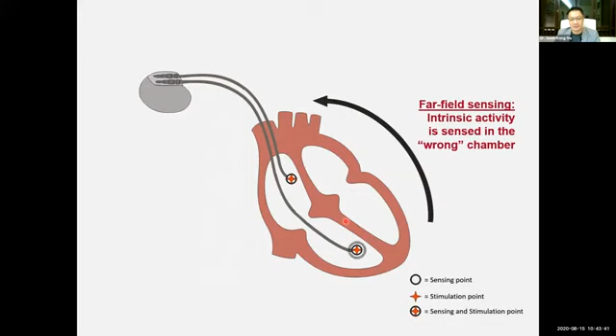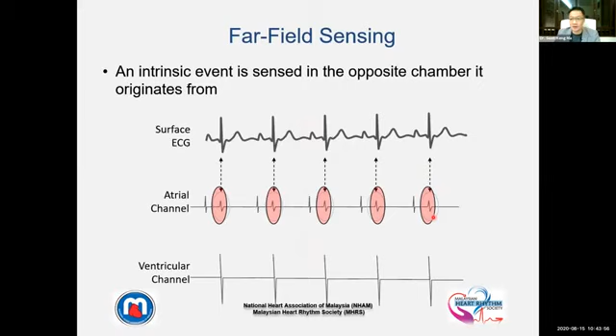And you can see here, the atrial channel always senses the QRS complex, which should be happening in the ventricular channel, but it picks up as a signal in the atrial channel. It looks like a 2-to-1 connection here. How to overcome this problem? Now, in the interest of time, I just move on. We skip the poll here. It is to increase the PVAB here, because you need to increase the atrial channel blanking period so that it won't sense the signal which is happening in the opposite chamber here.